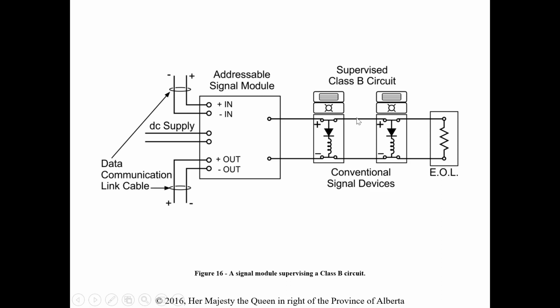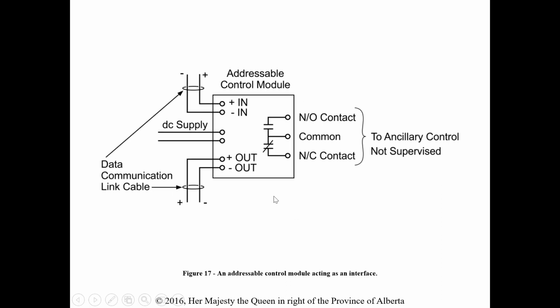Then we have addressable signal modules, pretty much the same kind of deal, except now we're talking about signaling devices. So these are conventional devices that do not have an address, so we cannot address them specifically with the system. So we can use a signal module in order to help with that. Again, we run DCL cables from the panel, and we potentially have a separate DC supply for that as well. So these could be, again, regular horn strobes that aren't addressable, but now they are because we have this module.